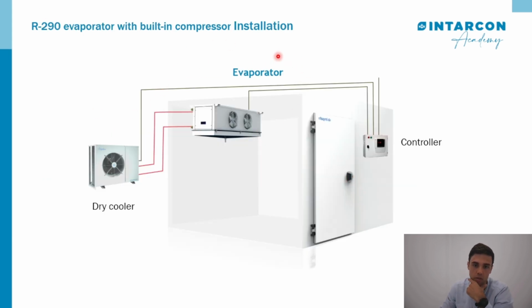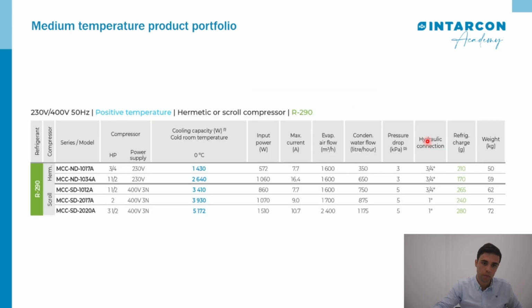Let's see an example of installation. Let's see this motor evaporator that cools inside the cool room, and the dry cooler that dissipates the heat that is generated in the part of the motor evaporator. In this case, the control panel regulates the unit. Let's see the main medium temperature portfolio product.